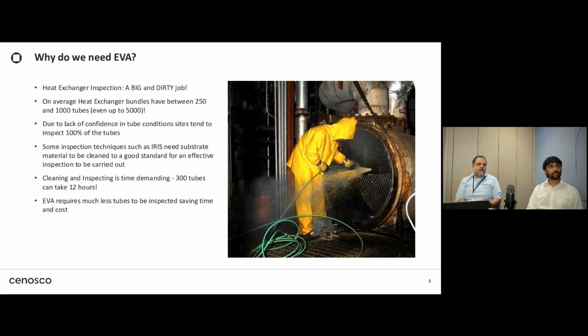In EVA, as we're going to talk about a little bit later, we use IRIS as the main inspection method, with a reliable outcome to do those calculations. We tried to do some case studies with MFL, for example, but it gives a different kind of outcome. So most of the time we're looking at IRIS, even though the cleaning required for an IRIS is bigger than for another method.